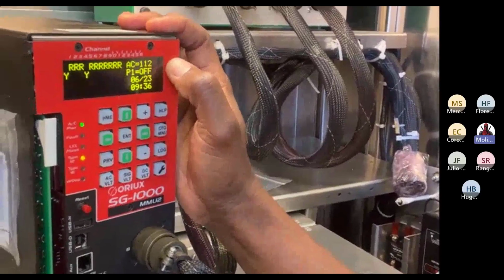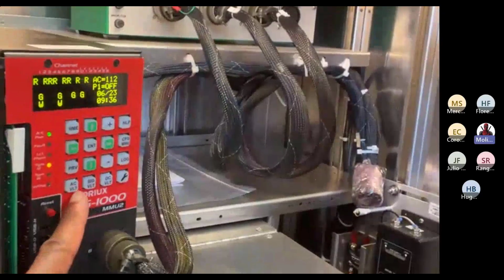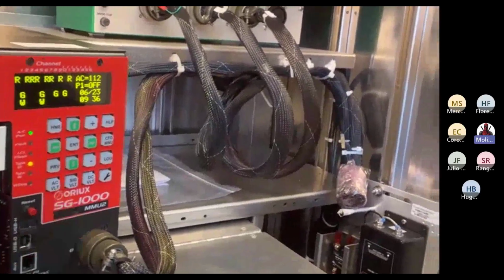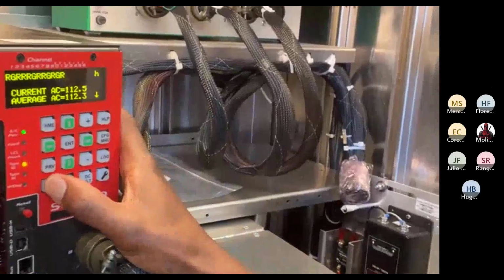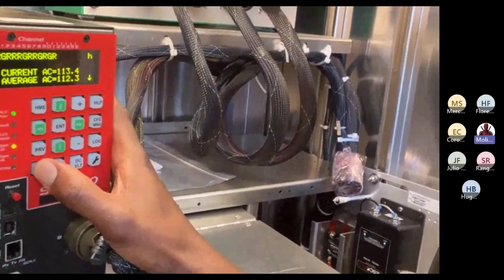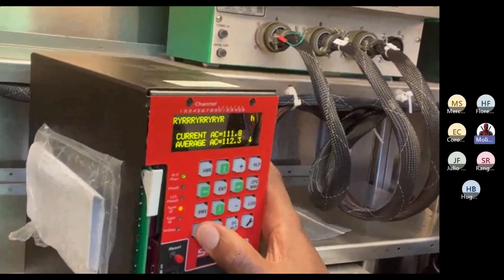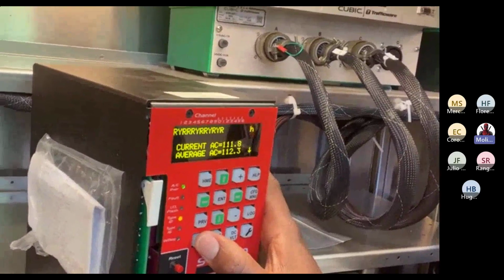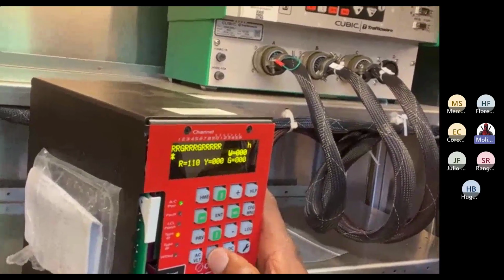Yeah, so it's constantly monitoring your AC on all your outputs. That's showing you the AC coming in. So if you want to see the AC going out, you hit the AC voltage button. So then you'll see all your ACs, right? Your lowest, your highest, average, things like that, right? If you want to see your signal voltages, there's a different button. The button just to the right of that will show you all of your output voltages on every channel.